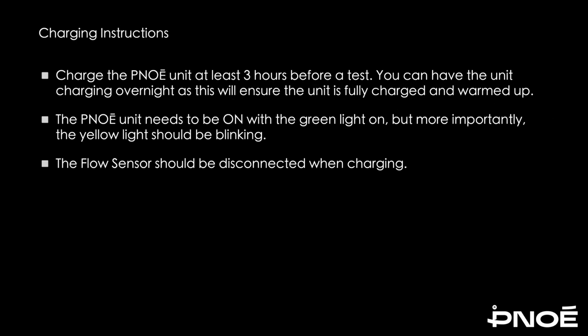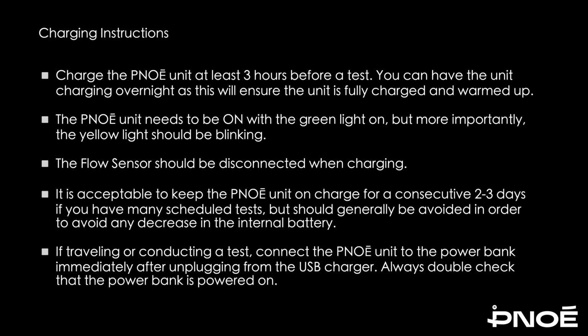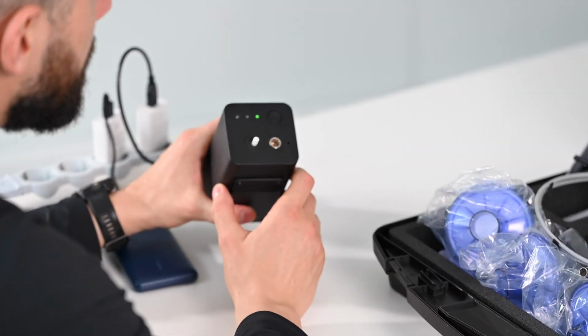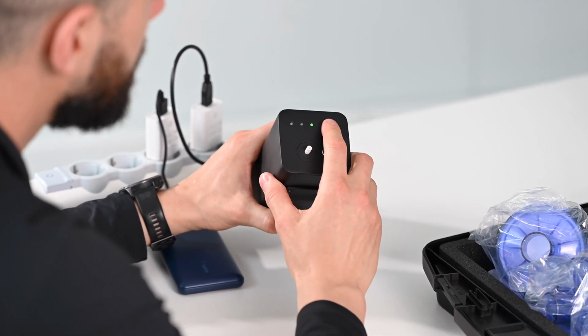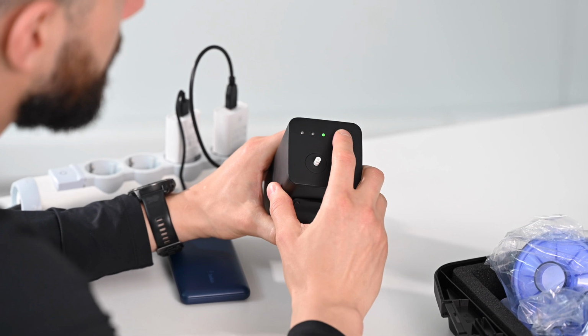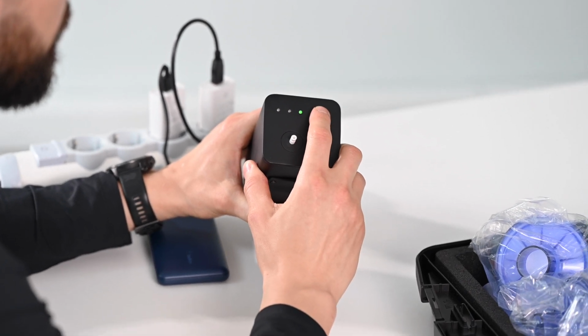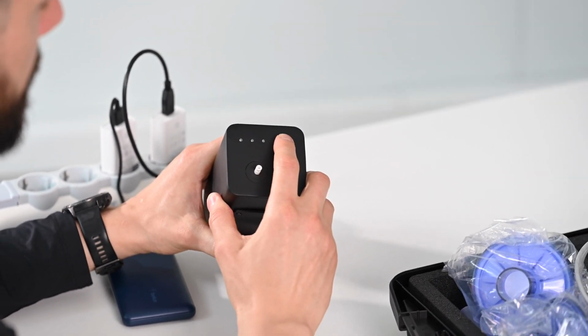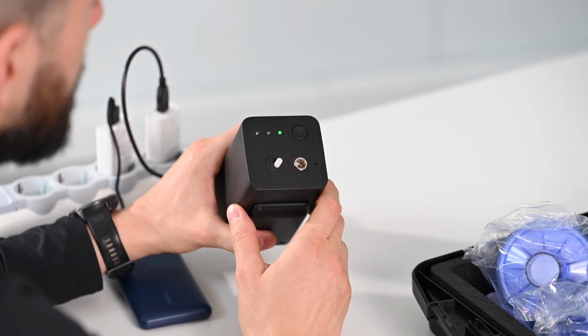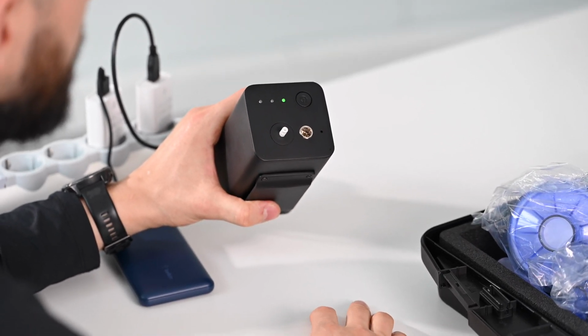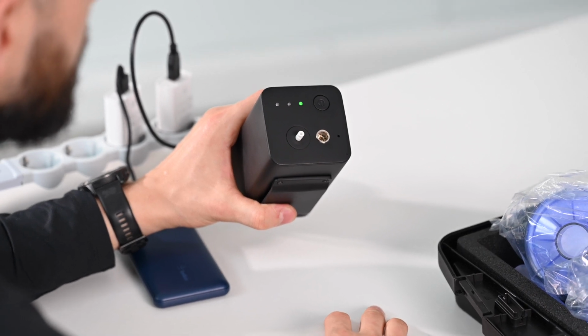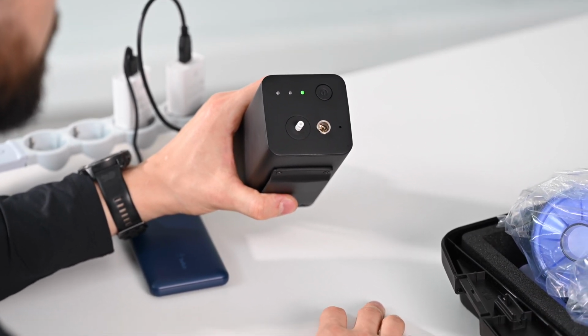If you have many scheduled tests, it is acceptable to leave it powered on and charging for even 2 to 3 days straight, but this should generally be avoided, as it will decrease the internal battery's life. If you ever notice that the green light is on, but the yellow light is not blinking, you should perform a hard reset. To perform a hard reset, press and hold the power button down until the green light turns off, and once it turns back on, release the power button. The yellow light will then begin blinking after 10 seconds or so.